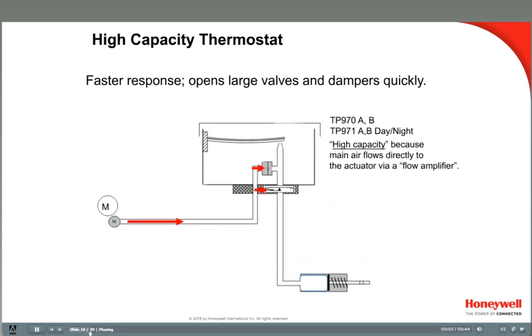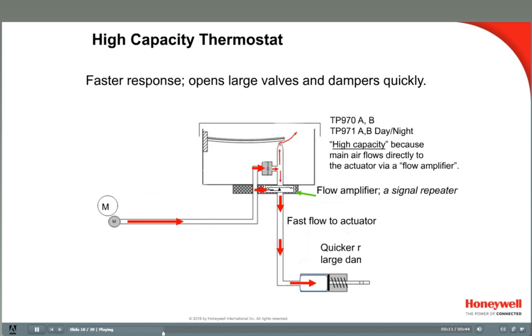The branch line output of a high-capacity thermostat responds very quickly due to the addition of a flow amplifier. Main air still travels through the restrictor to the nozzle bleed, but it also flows to a flow amplifier module prior to the restrictor. The nozzle pressure acts against the flow amplifier diaphragm, which repeats this signal into the branch line with high-volume air from the main air supply. This positions actuators quickly, providing fast response to changing loads and larger actuators. Most installations today use high-capacity thermostats, such as the TP970 or TP971 day-night stats.